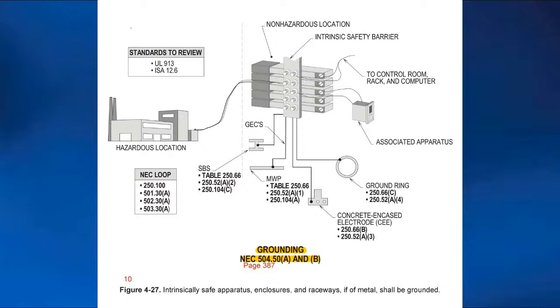I always like to look, and you grounding experts out there should too, at 250.50 and 250.52, which describes what can be used as an electrode. And then you electricians install those electrodes per 250.53. Yes sir, it's laid out beautifully in a systematic order: 250.50, 250.52, and 250.53.